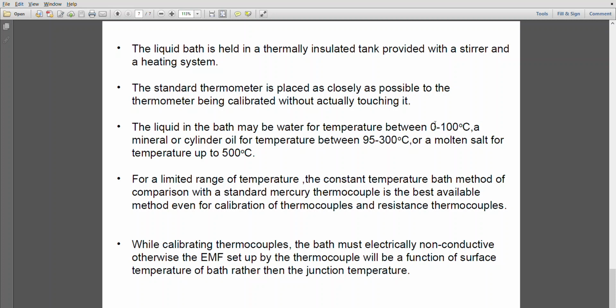For a limited range of temperature, the constant temperature bath method of comparison with a standard mercury thermometer is the best available method, even for calibration of thermocouples and resistance thermometers.